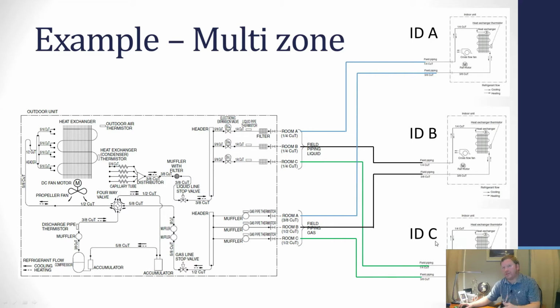Now, the other thing you have to be really careful about with mini splits, which we'll talk about in another video when we focus on the install, is making sure that indoor unit A, indoor unit B, and indoor unit C all get piped to the correct ports. If you cross these ports, then you're going to have a total disaster. But again, we'll leave that for another day. All these indoor units are getting that hot gas. You can see that there's no valves preventing that hot gas from getting to the indoor units.